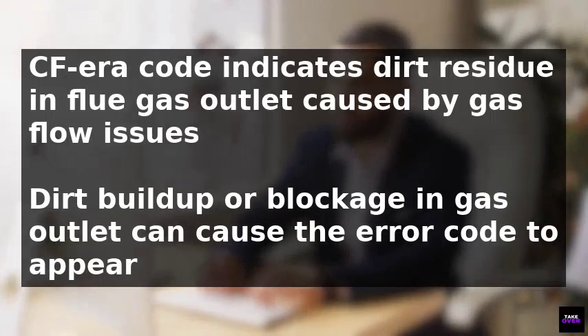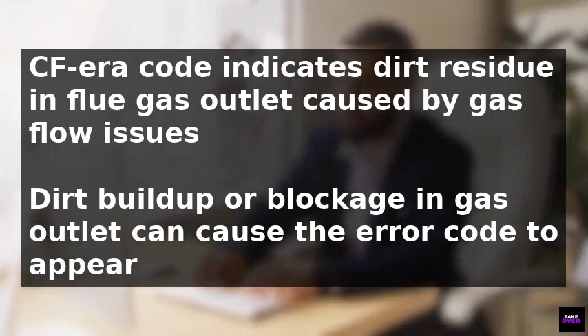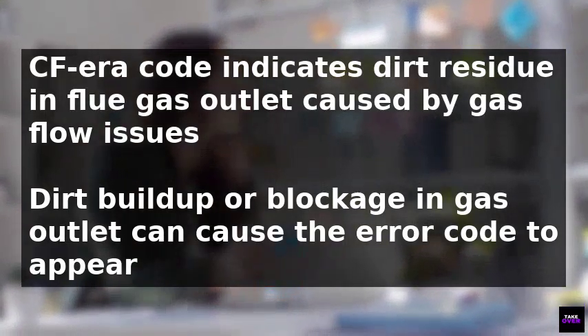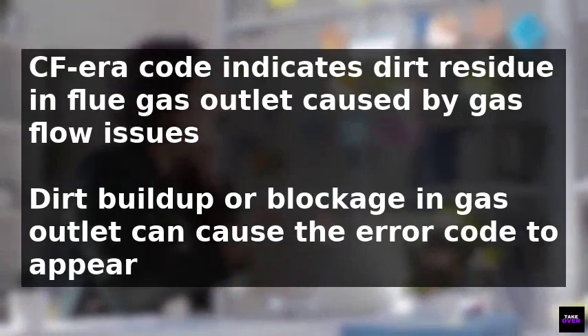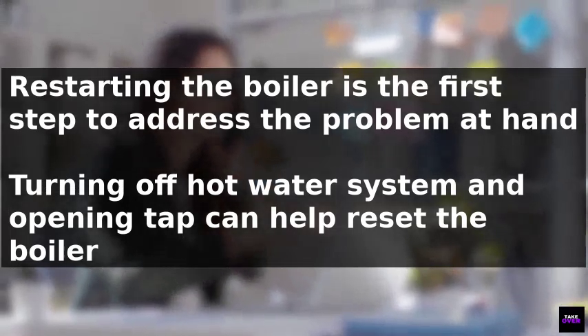The CF error code on a Bosch boiler indicates an accumulation of dirt residue in the flue gas outlet. This issue can be caused by several factors, including gas flow hindrance, dirt buildup in the gas outlet, or a blockage of the gas outlet. To address the problem, restarting the boiler is a good first step.